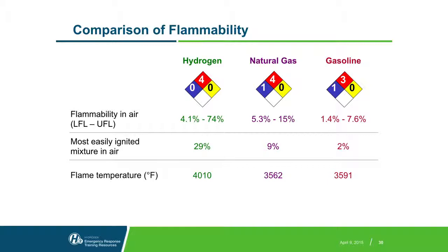The point here is, however, that the hydrogen gas sensors that are employed in vehicles, at fueling stations, in this unit that's being deployed, is that they are calibrated and will alarm at levels that are very conservative and much lower than this lower flammability limit. And actually this 4% is not an absolute number. There's a lot of variables that go into it. And I've been told recently that actually flammability doesn't begin until about 7 or 8%. But suffice it to say that the hydrogen gas sensors will start alarming somewhere in the neighborhood of 0.4% hydrogen and air, and ultimately shut down the system at around half of that LFL. So about 2% in air.